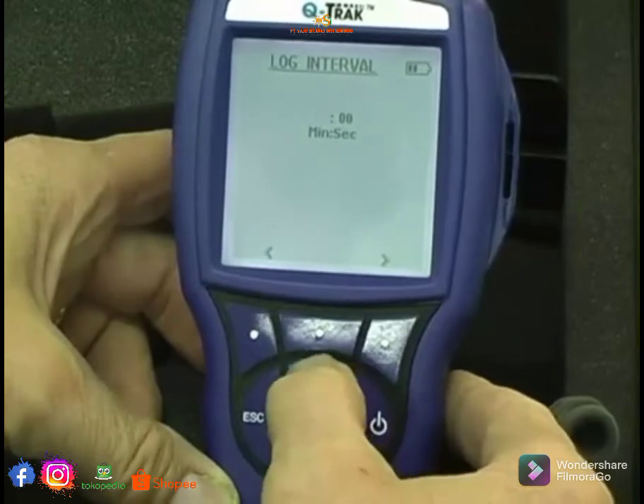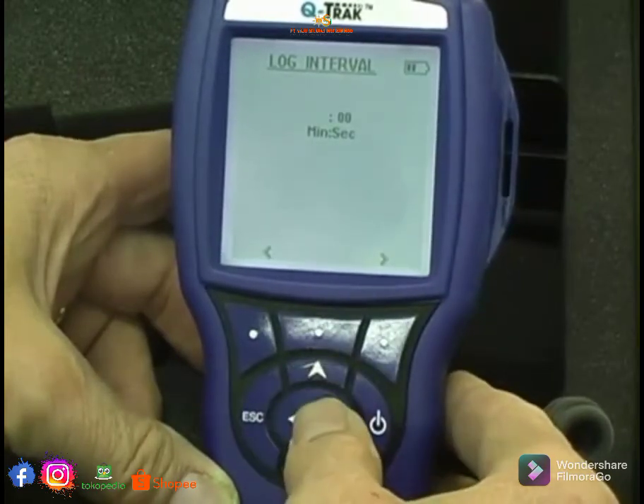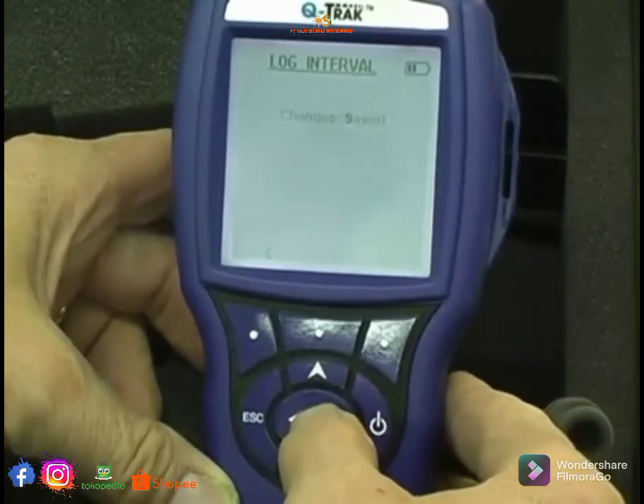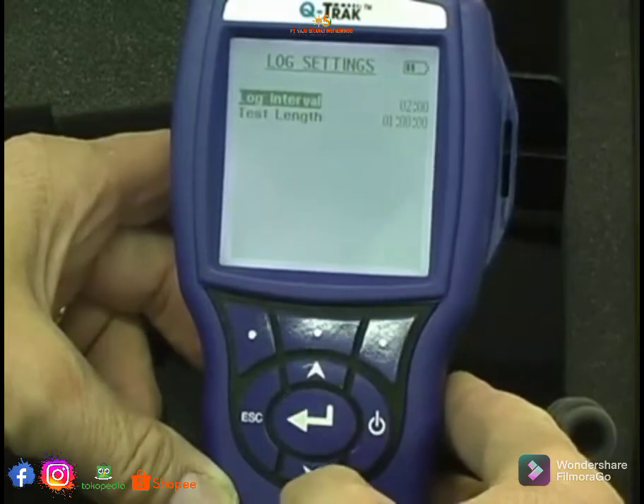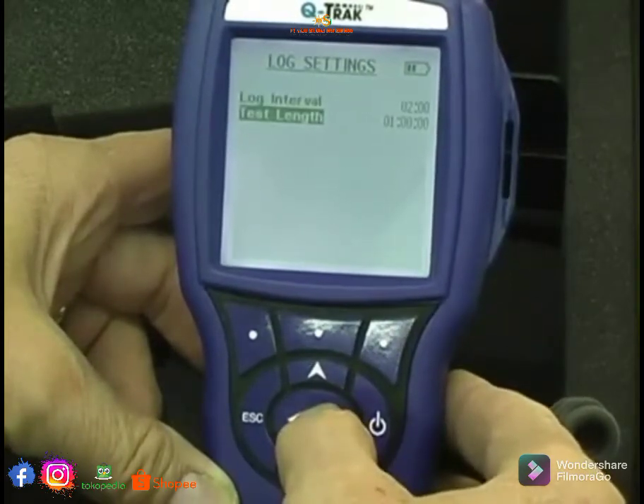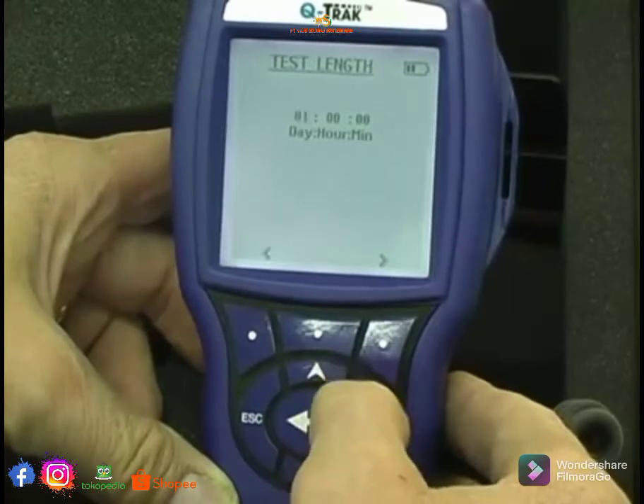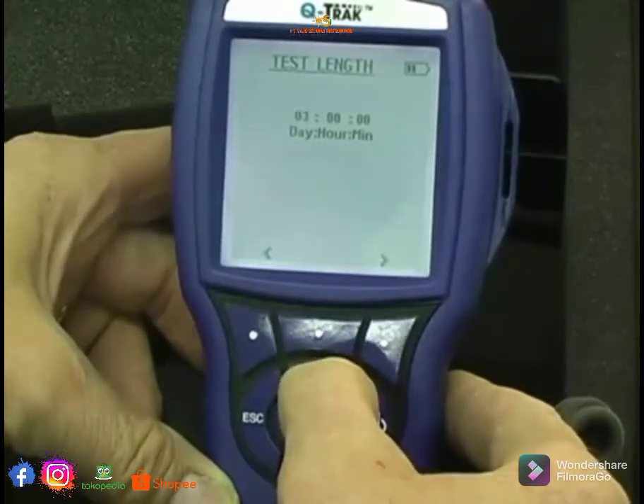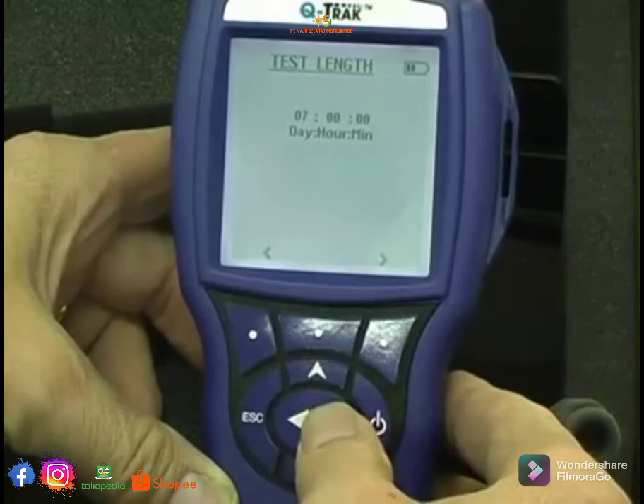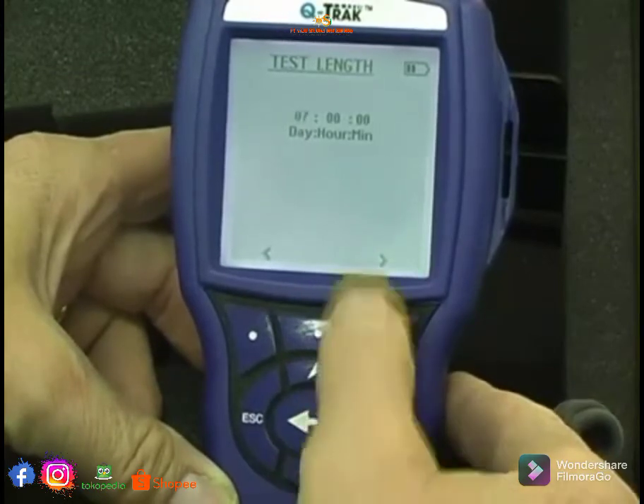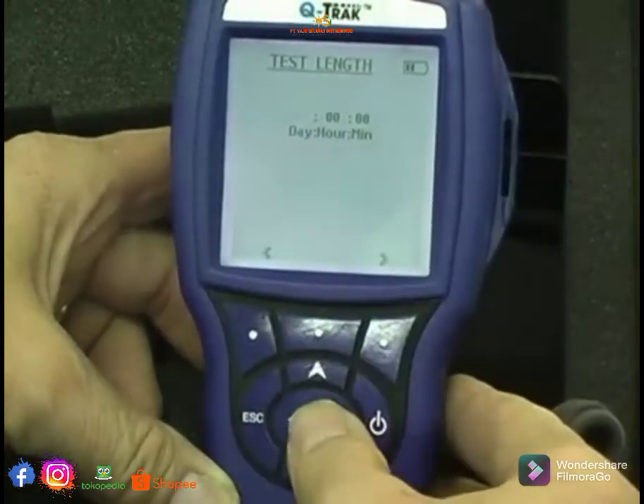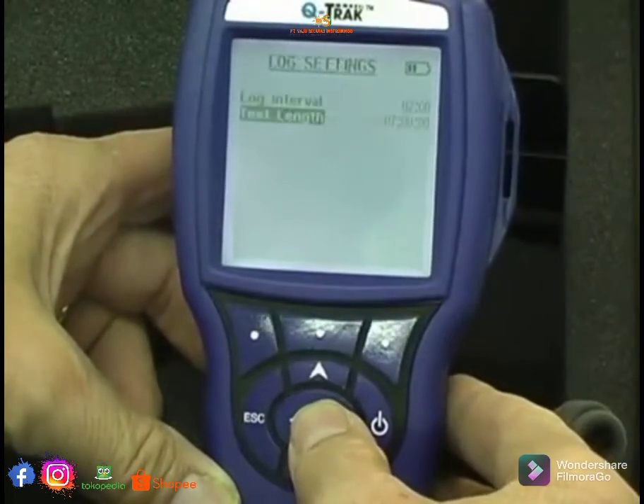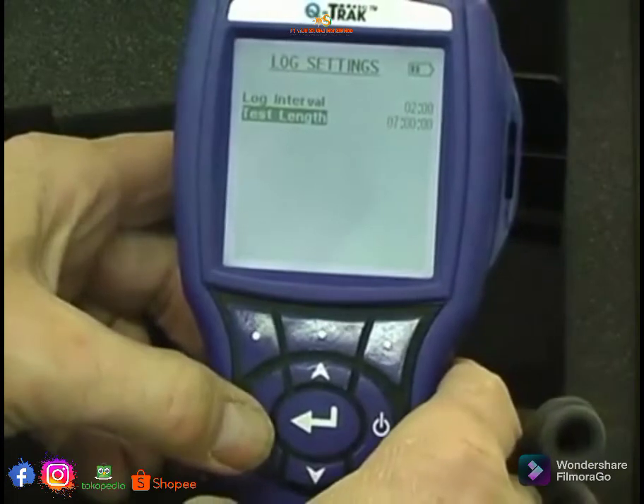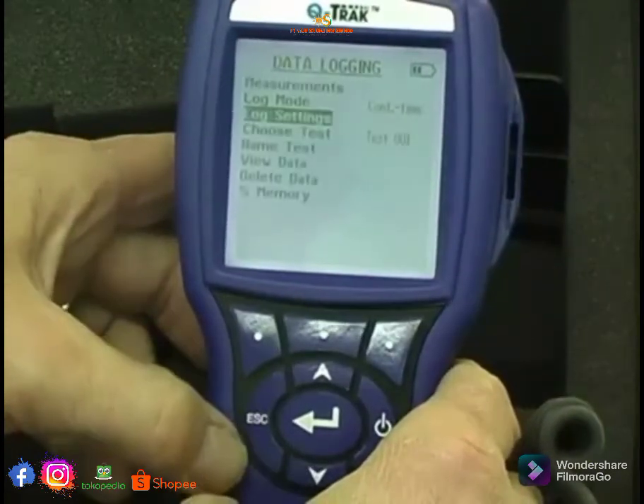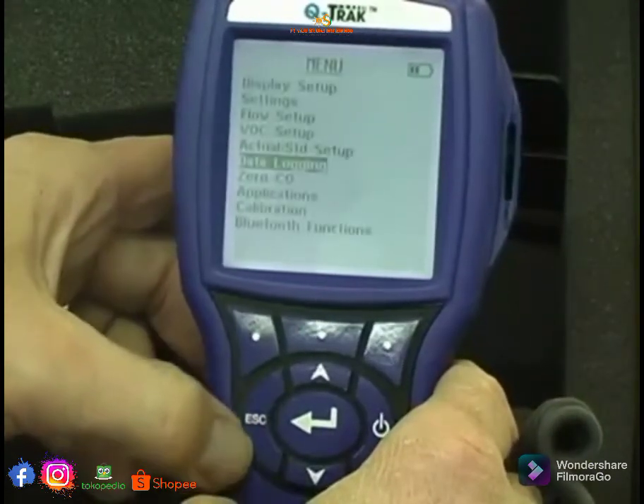So if we wanted to change it to a 2-minute reading, I would set it to 2, I use the up arrow. Now I'll push enter to save those changes. Now the test length, if we wanted to measure it for a week, for example, 7 days. And we go enter. Now I can change the days, hours and minutes appropriately, and I push enter to save the changes. Now I've modified that to 2-minute intervals for 7 days. Now I hit escape to get out of there, and escape again and escape.